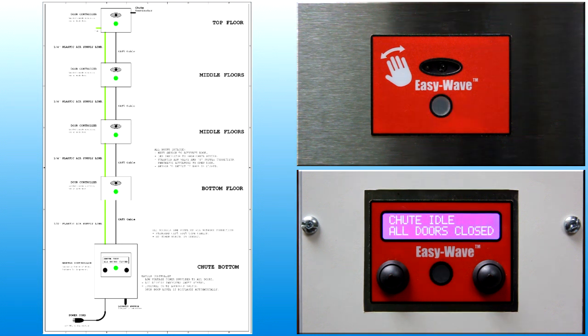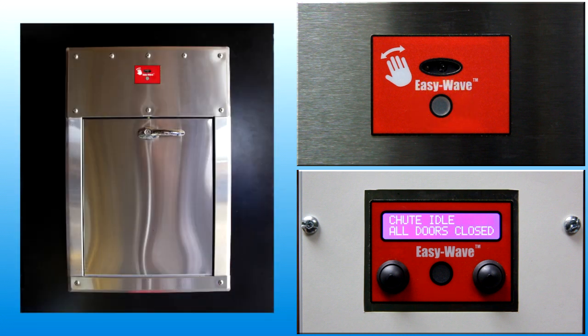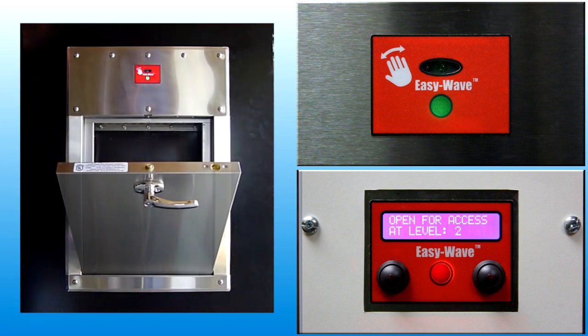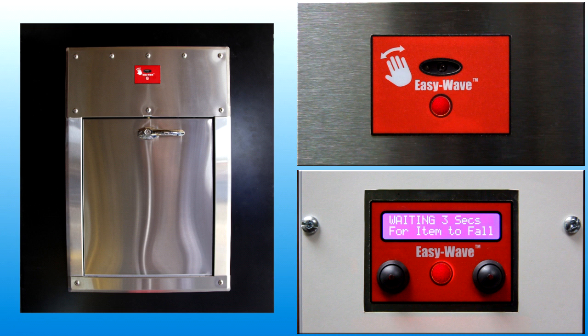User feedback about the operating status of the chute is provided by the LED indicator. When the light is off, the door is locked, the chute is idle, and waiting for user input. When the light is green, the chute is ready, the door is unlocked, and may be opened. When the light is red, the chute is busy, the door is locked, and user input is ignored.